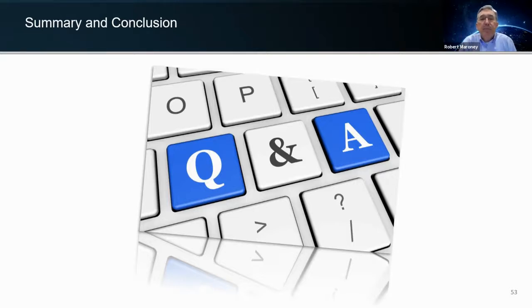Go ahead, Scott. There was another question, and this is a really good question because there's a lot of confusion out there. What is the main difference between this and the Vycon solution? When you look at the Vycon solution, just so you guys know, Vycon has left the United States. It was acquired by a Chinese company, so they're all manufactured in China now, in Shenzhen. It's a magnetically levitated flywheel energy system. So they have a 5,000 RPM liftoff bearing to get the flywheel up to that speed where they can generate enough magnetic field to lift off the bearing and then drive to their nominal speed anywhere from 40 to 55,000 RPM.